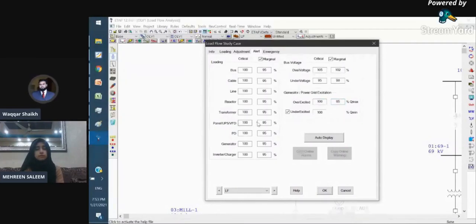For active power, it will give you overloading alerts, which are shown here. This is the overloading alert. This region is called the overloading alert, where we have 100% to 95%. So for example, if the generator is able to deliver 100 kilowatts and your load is trying to draw 105 kilowatts, the generator will run into an overload condition.